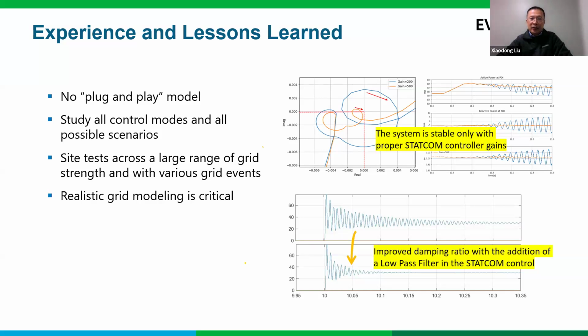The preliminary study should include the voltage step test, function step test, phase jump, and the different faults close to the STATCOM. The STATCOM response time, the overshoot, settling time, overvoltage, overcurrent, and so on, should be compared with the different control parameters, like controller gain, slope, and protection settings, to make sure that the STATCOM meets the basic performance expectations, is stable, and has no voltage exceeding insulation level. So the manufacturer's default model has never been plug and play. They always have something to be adjusted before more detailed studies are performed on the actual system.